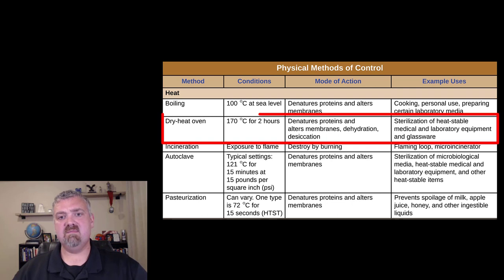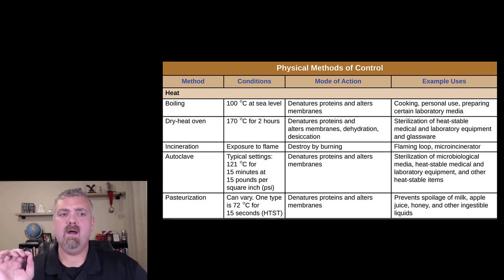Then we have dry heat, comparing that to moist heat. Dry heat, for the reasons I said before, takes a lot longer and a higher temperature. Dry heat can sterilize things, but it takes 170 degrees for two hours. If you have the time and things are heat stable enough to use a dry heat oven, then it's very effective. But as an equivalent treatment, it takes 170 degrees for two hours to do what an autoclave can do at 121 degrees for 15 minutes. As you can see, moist heat is quicker and generally more effective.